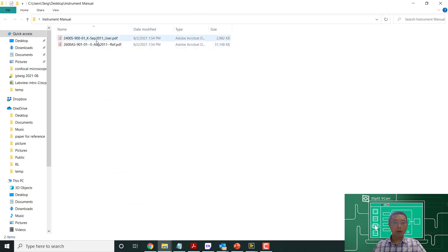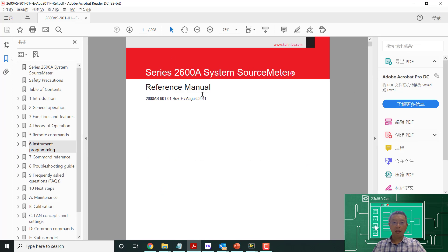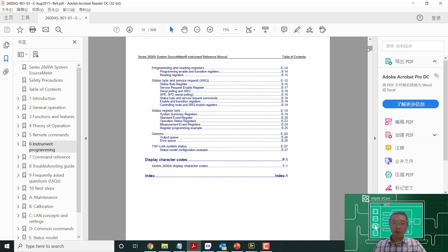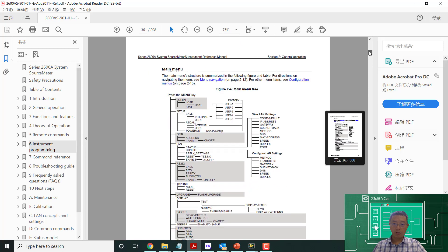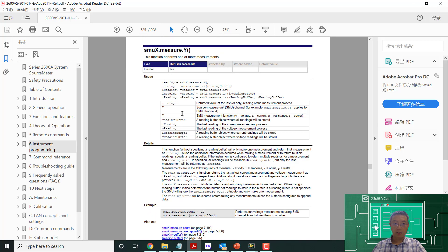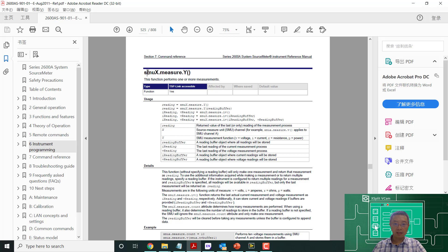We're going to look at the manuals — for example, the manuals for the 2600 and the 2400 series. Although these manuals are very long, in each section they put a lot of information regarding how to use the instrument. For example, it says this is an SMU measurement: if you're using SMU X and measurement Y, you can see how the measurement can be done. We only have one channel, so this is going to be SMUA, and we measure some numbers, and then we can program this.